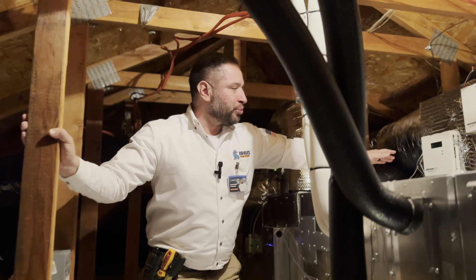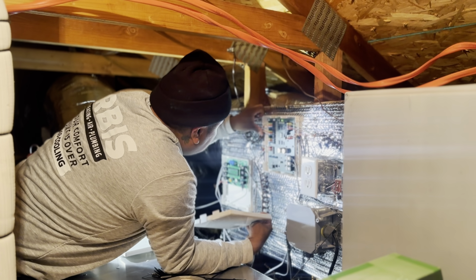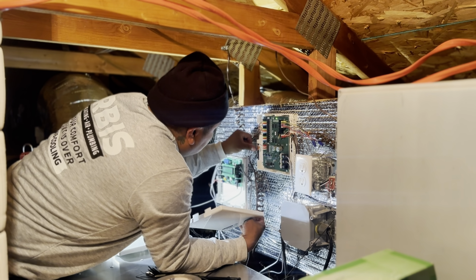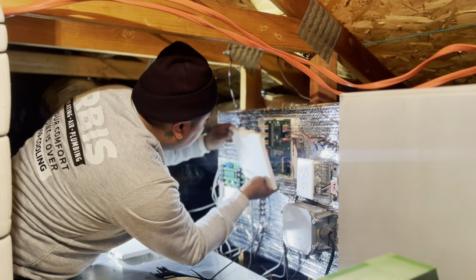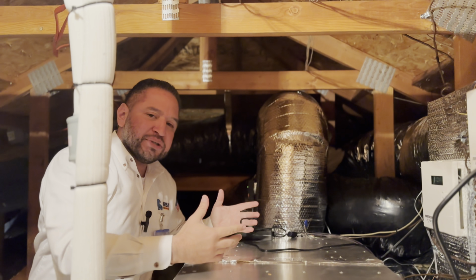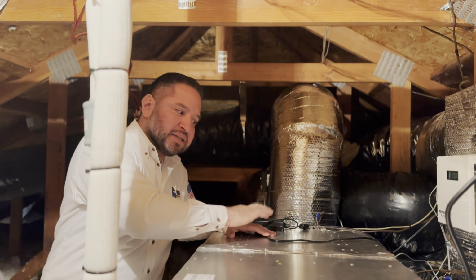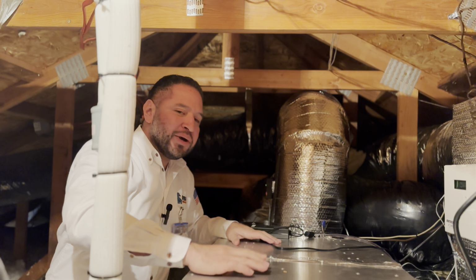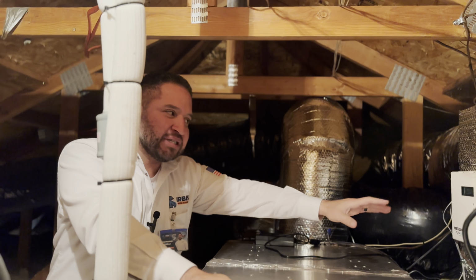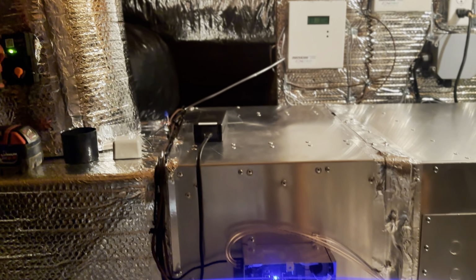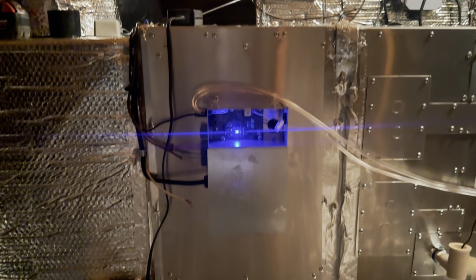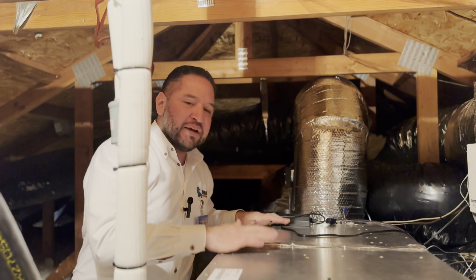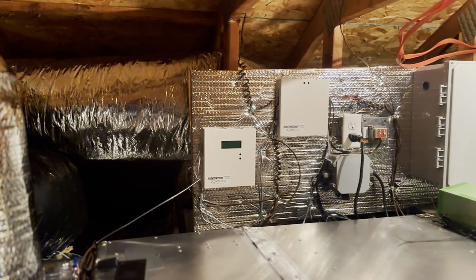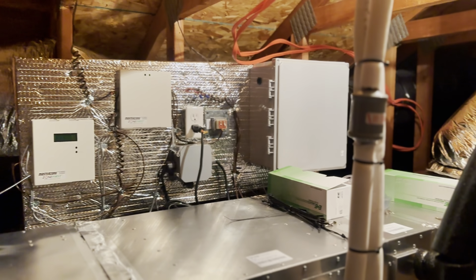Here's one portion of the zone control board. This is what's connected to the actual electronic dampers that are going to open and close based on the demand of the thermostat calling for heating or cooling. And if you look a little bit closer here, we no longer do what used to be referred to as a bypass system. When you would zone it, pressure would build up and you had to do a duct connecting from the return to the supply side. We no longer have to do that. With the zone first system, this is what we call the bypass eliminator. It monitors the static pressure and regulates the dampers to open and close slightly with a slight bleed if the pressure builds up, keeping the airflow nice and smooth, protecting your system, and making sure that everything's working properly.